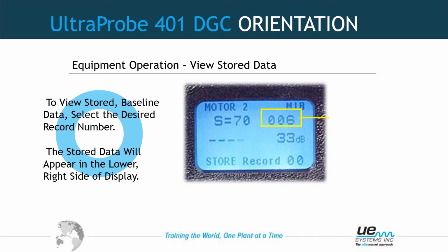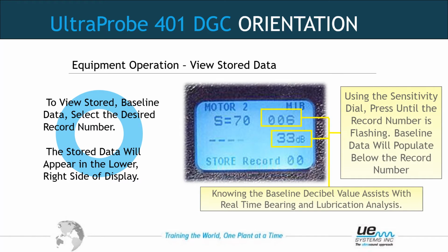To view stored or baseline data, select the desired record number. So here we select record number 6, and then we will see the baseline data. There's no current data yet, but we can even skip ahead to record number 7 and see what the baseline is, record number 8, see what the baseline was before we store any information. Using the sensitivity dial, press until the record number is flashing. The baseline data will populate below the record number, which is the dB from the baseline. Knowing that baseline decibel value assists you while using real-time lubrication methods of ultrasound.